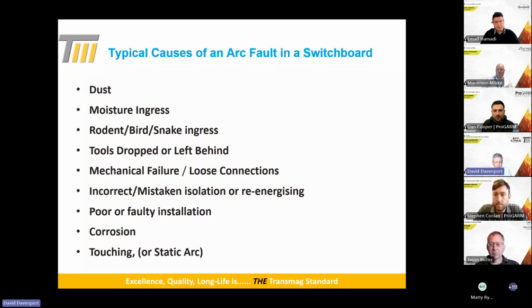And the other one is mechanical failure and loose connections, usually because many switchgear substations do not have the maintenance routine recommended by the OEMs of the particular breakers, etc. It's seen as an economic saving without actually gaining anything. Well, it's the losses they ought to be considering rather than the gains.